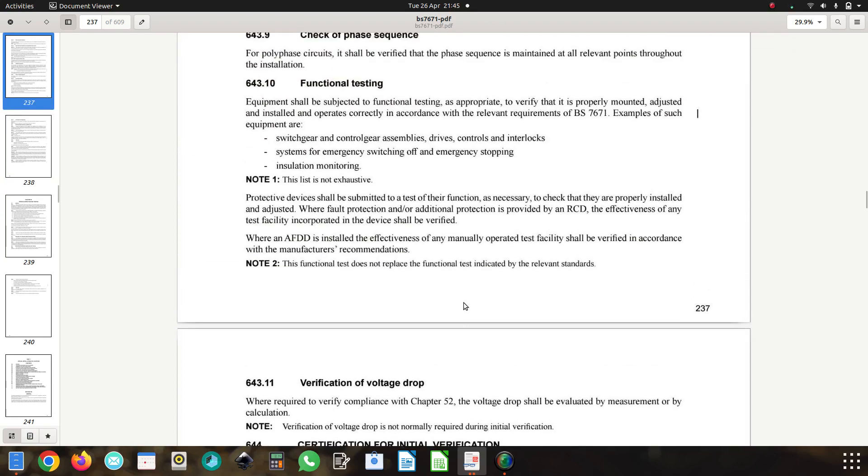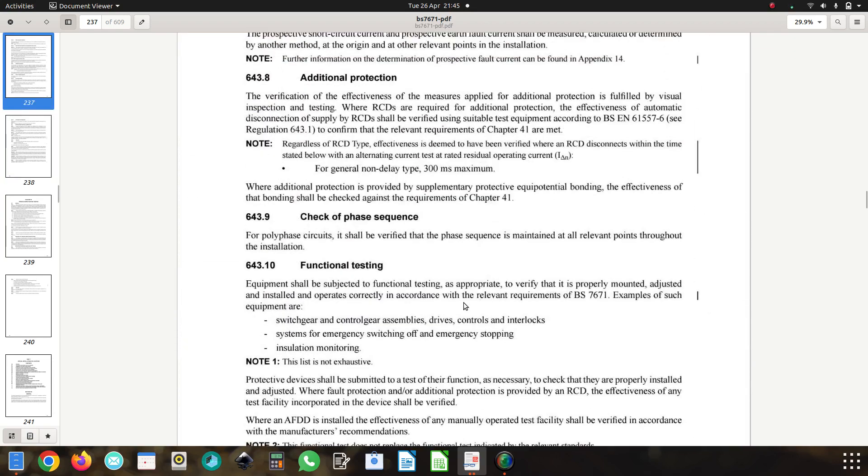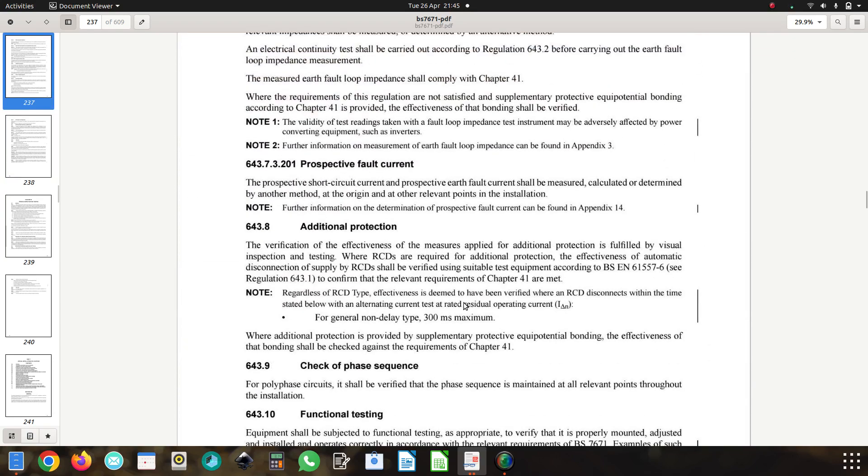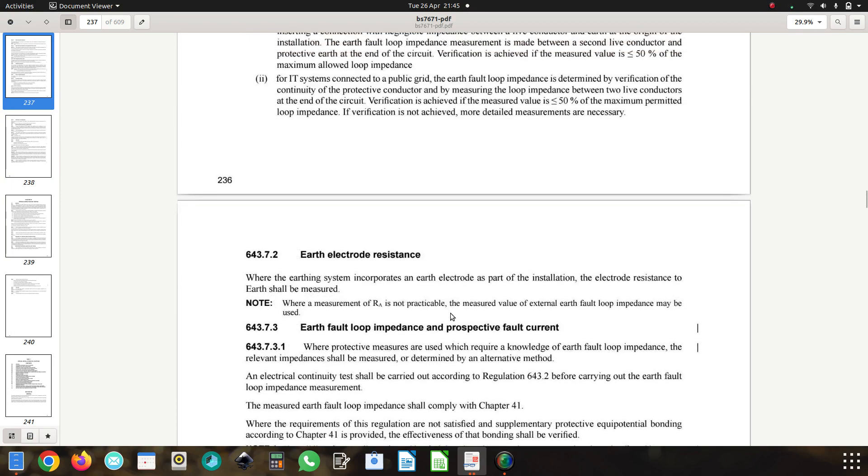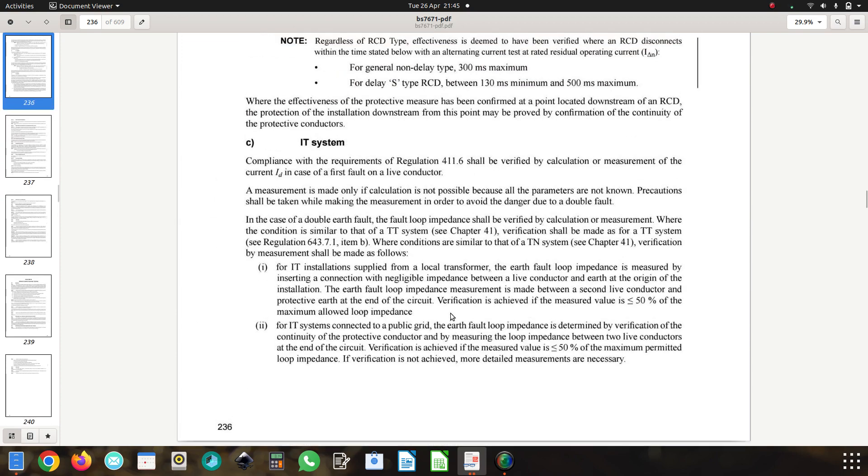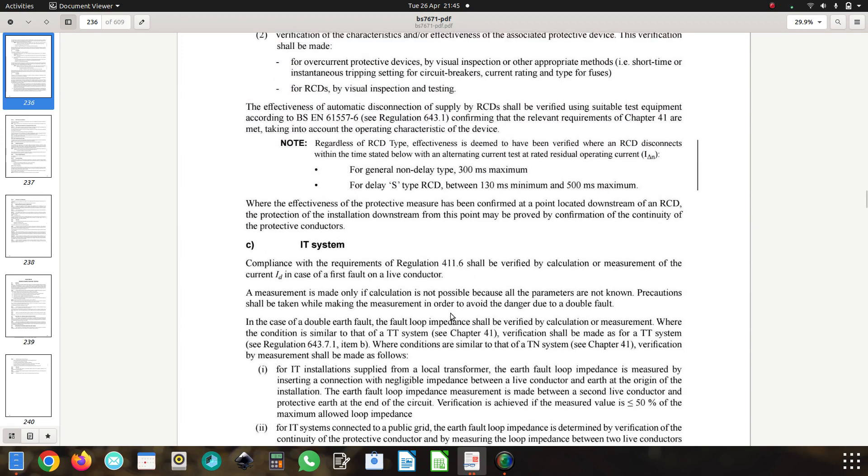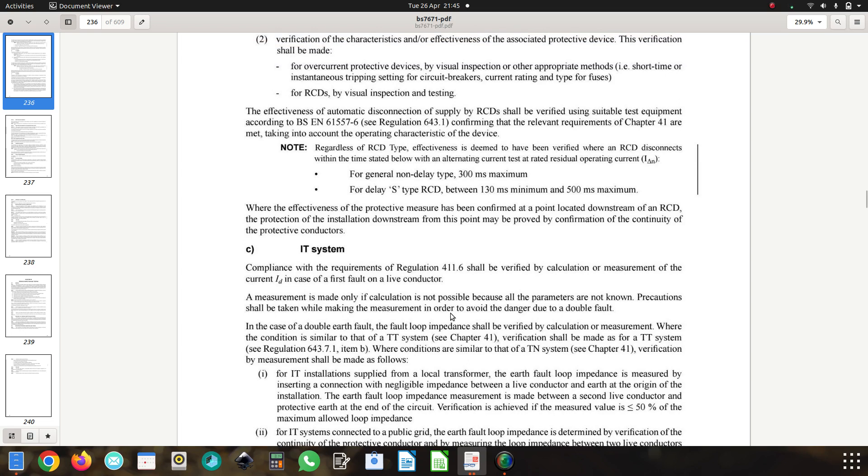For TN systems we've got 300, and TT—here we go—for additional protection. Well it is additional protection, but it's not fault protection. We're looking at fault protection. So anyway guys, love to know what you think about it. Any comments, feel free to post. Thanks very much for watching.